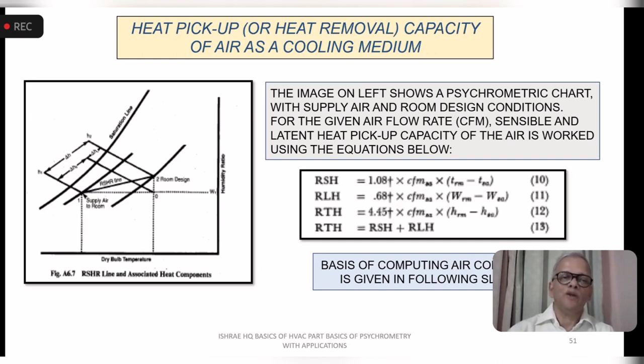In the same way, we are supplying that air at a moisture content of so much. The room latent you have worked out, and you know the air quantity. So with that much air quantity, how much latent will be added, how much moisture will be added, and what will be the resultant room moisture level, and is it falling within the specified limit? So you are getting these resultant values based on your selected capacity. If it is falling within the acceptable limits with the tolerances for all the spaces, you do not anticipate any problem. But if there are some spaces where the resultant room conditions fall outside, you may have to take some corrective action locally.